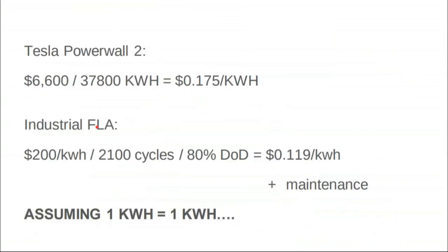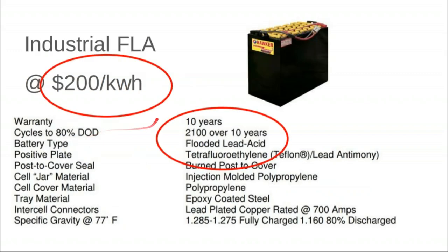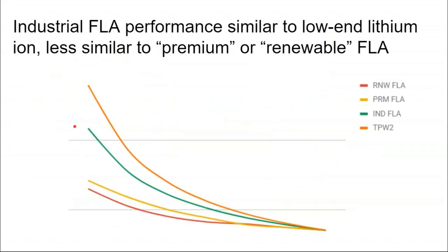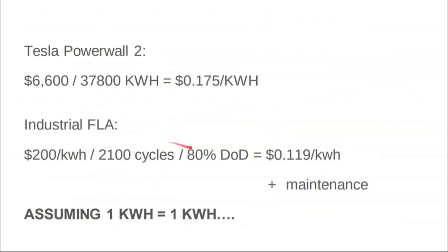So let's talk through some numbers here. The Tesla Powerwall 2: $6,600 of parts, 37,800 kilowatt hour warranty. That comes out to be 17.5 cents per kilowatt hour. Industrial flooded lead acid is $200 a kilowatt hour, rated for 2,100 cycles at an 80% depth of discharge. And so that turns out to be 12 cents a kilowatt hour plus maintenance.